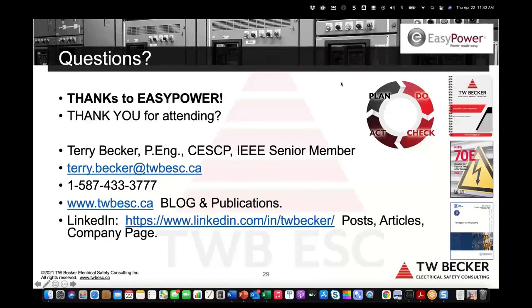The way I frame that, and I didn't have this in my slides, is that the arc flash boundary is really a safe zone. It's a safe zone where you don't need any PPE. So the working distance is this at-risk distance for the worker's face and torso, but they've got arc flash PPE on because they did their arc flash risk assessment and defined additional protective measures, which was determining the PPE from the equipment label, if we have the studies completed on the electrical equipment.